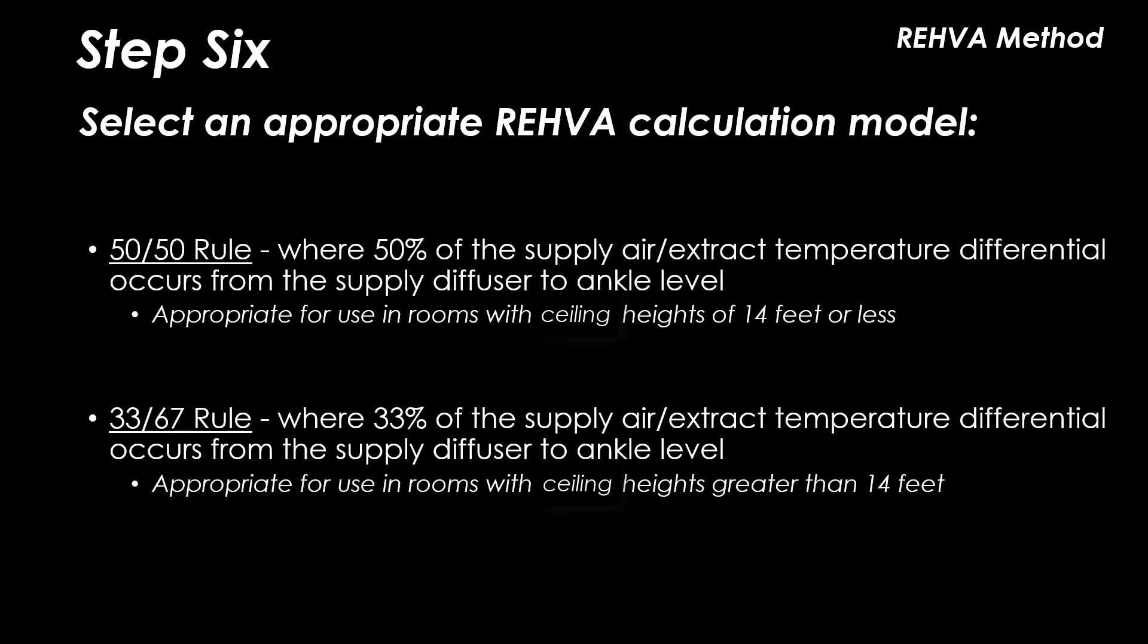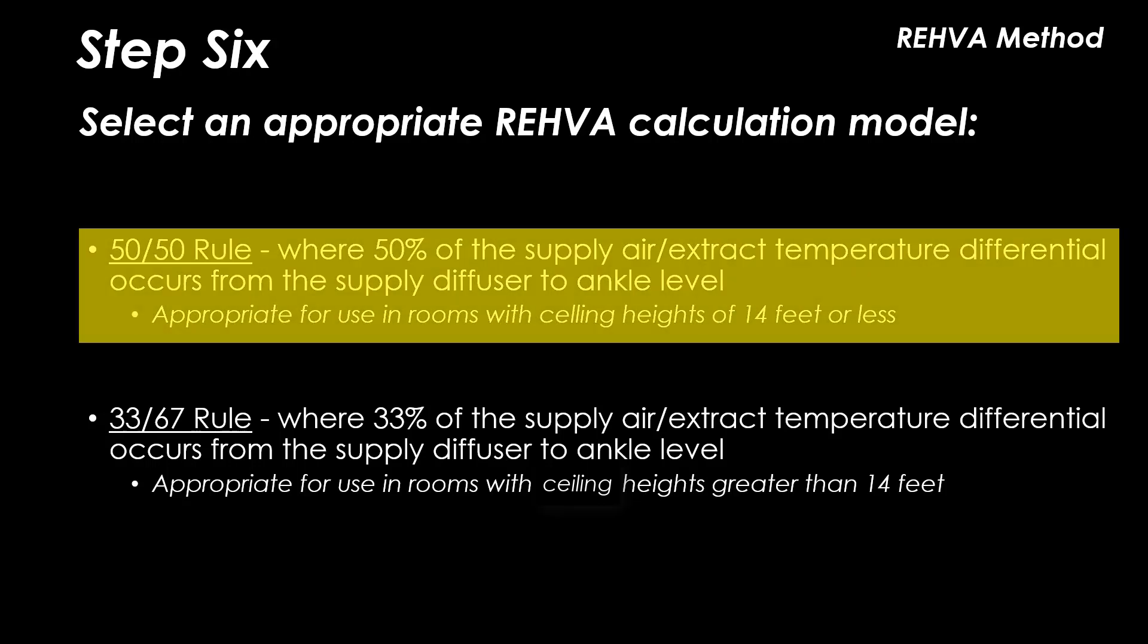In step six we will choose an appropriate REHVA calculation model based on the room height. There are two models. One that refers to rooms with a normal ceiling height, which can be taken as around 14 feet. The second model refers to rooms with high ceilings, which should be applicable for entrance lobbies, airports and atria. We will be using the 50-50 rule as our classroom has a ceiling height below 14 feet.